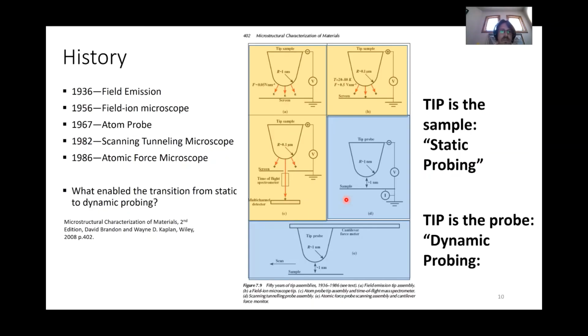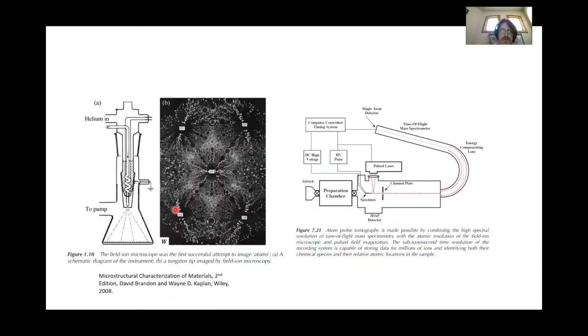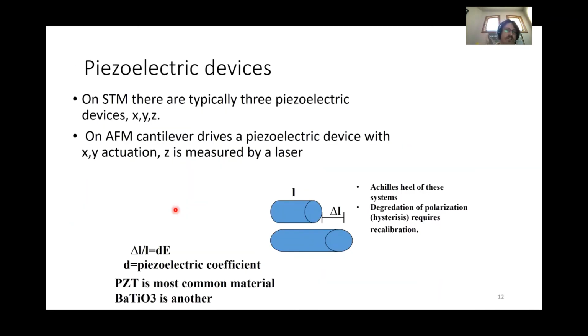Kind of going back to my question here, I couldn't read my own writing, so to speak. What enabled the transition from static to dynamic probing? We'll answer the question now. Piezoelectric devices. And so on a scanning tunneling microscope, there's typically 3 piezoelectric devices in the X, Y, and Z. On the AFM, the cantilever drives the piezoelectric with X and Y actuation, and Z is measured by a laser, basically. And piezoelectric, we'll kind of just give a really quick overview.